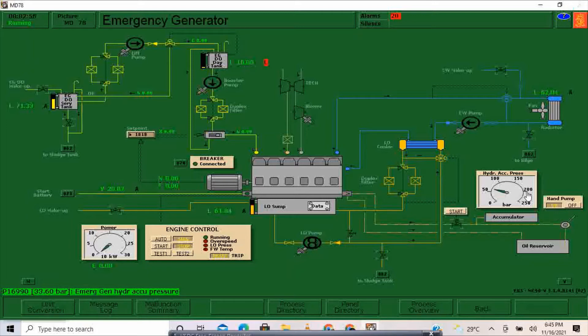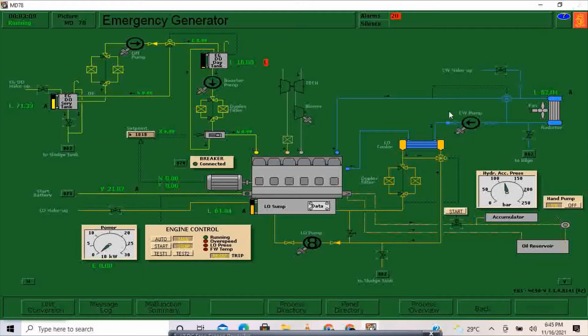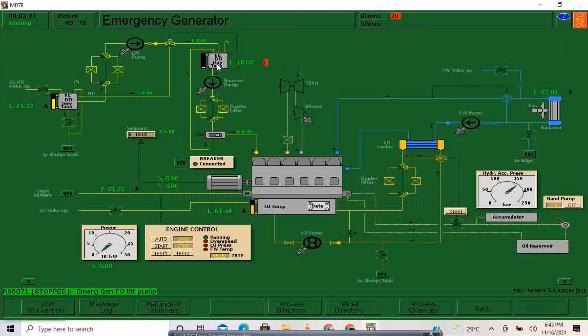This is a low level alarm on our diesel day tank. It will be topped up when our emergency generator is already running, because these are shaft-driven pumps. Once the emergency generator is running, this transfer pump or lift pump for the diesel oil will also run, and diesel oil will go to that diesel oil day tank.